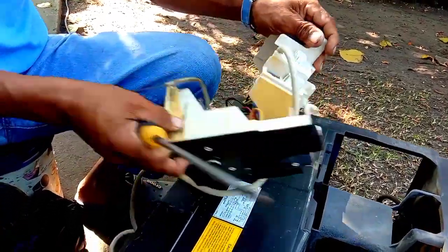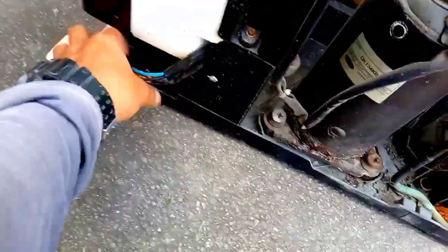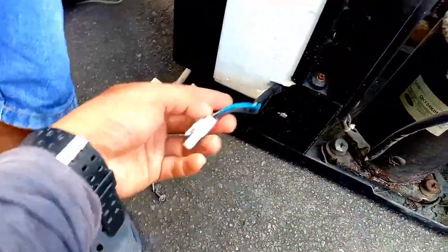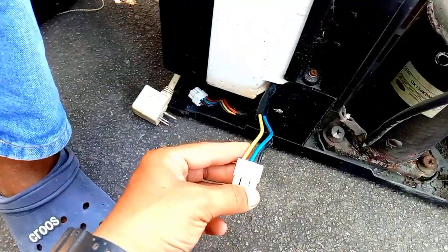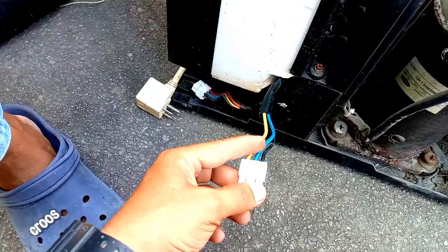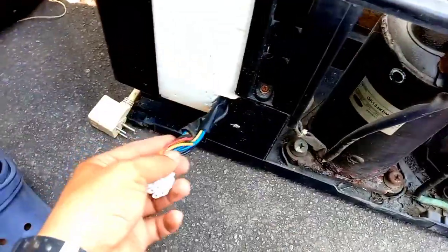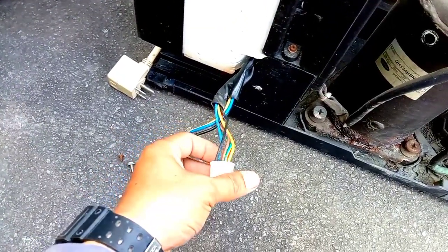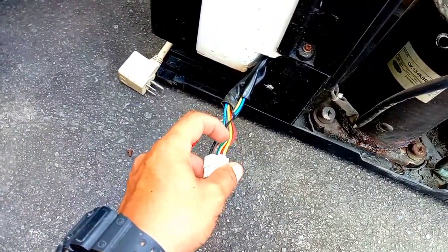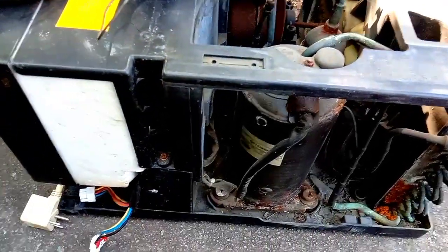We're going to get that first, then condemn it to get another capacitor. Those three wires, yellow, blue, and black, are the connection wires from the compressor of the unit, the common, starting and running of the compressor. Then those five wires, black, brown, blue, yellow, and green, are the connection wires from the fan motor of the window type unit. So we are going to condemn, bypass it.